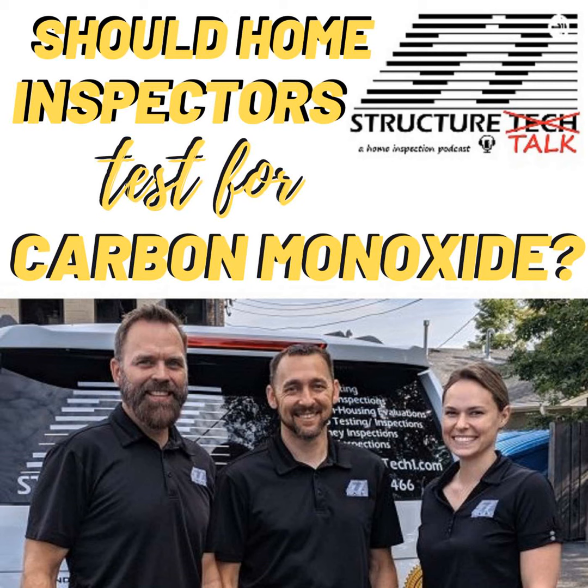Okay. There's one other hard and fast rule. And so I'm going to throw this softball up to you. Where do we always know that this is a bad furnace? When it's a Lennox Whisper Heat. Whisper Heat. Yes. Okay. Apparently my softball was not as big as I thought it was going to be. Okay. It's right. 400 parts per million in the exhaust gas.